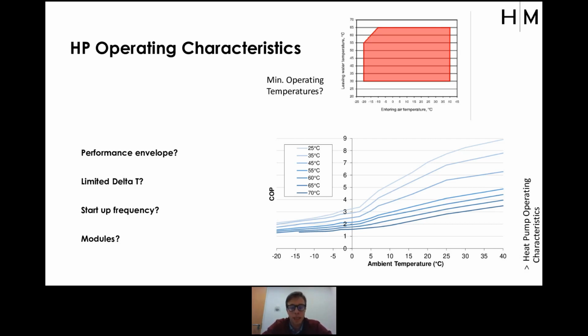But some of the key things here, in terms of air source heat pumps, if you're adopting those, is the outside air temperature effects on COP. And if you're operating at higher temperatures, this further penalises you in terms of operating efficiency. So you can see in the bottom right diagram, it quickly drops at the higher temperature. And this is representative. It's obviously many different technologies, different refrigerant types that have different performances, but it's worth looking at these early enough, because they do have different spatial requirements or different design requirements you need to consider, which some of these things will come on to.